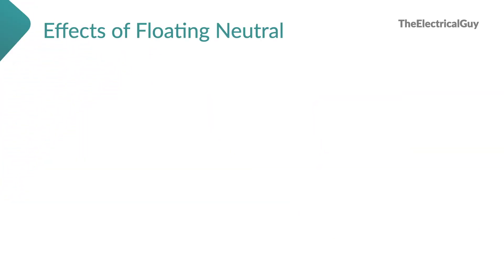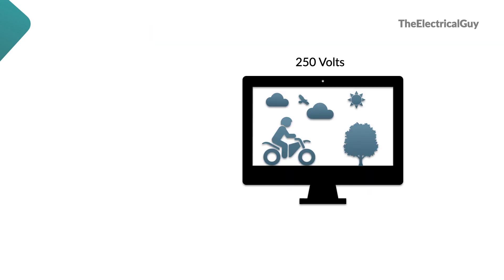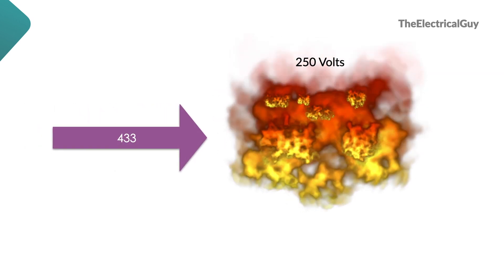Floating neutral can be very dangerous. It causes very high or very low voltage across the load. Load connected phase-to-neutral can experience maximum voltage of phase-to-phase, which in our case is 433V. So if you see here, our appliance or any device connected across phase-to-neutral is designed for 250V. But now it may have to face 433V. Definitely, this high voltage will damage the device.